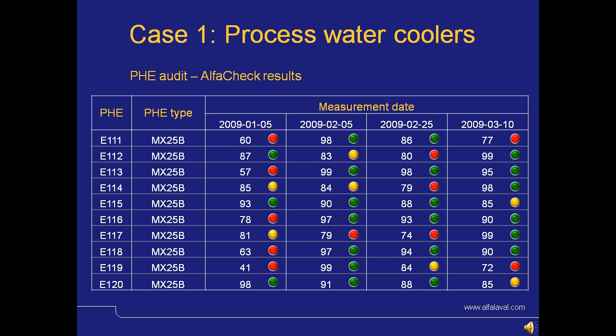As I mentioned before, AlfaCheck is a service that lets us check the performance of the heat exchanger without opening it. Each of the boxes represents a percentage of the performance of that heat exchanger at that time of measurement. Looking at the first column, we can see that not all heat exchangers were as badly fouled. For example, number 2, number 5 and number 10 are in pretty good shape, and they do not need to be cleaned right now. The green light represents a heat exchanger in a good state, yellow in a state where we need to prepare for service, and red in a badly fouled state where we need to clean it. Based on this measurement, we decided which ones needed to be cleaned. For example, number E111, E113, E116, and so on.